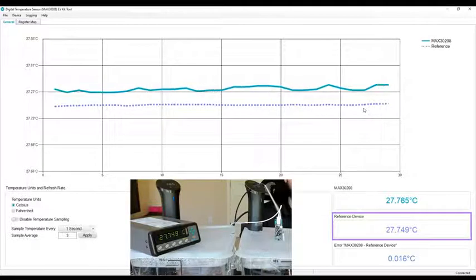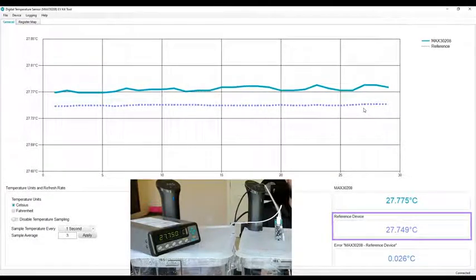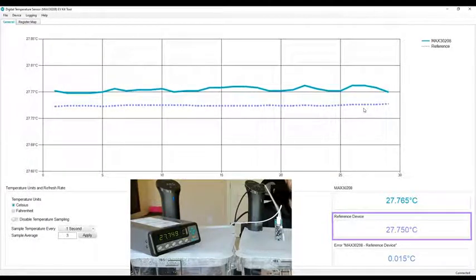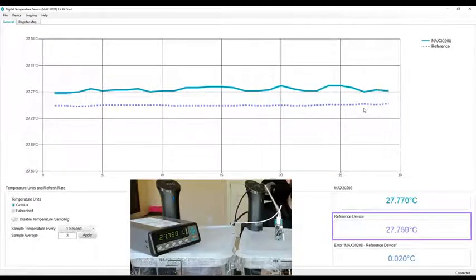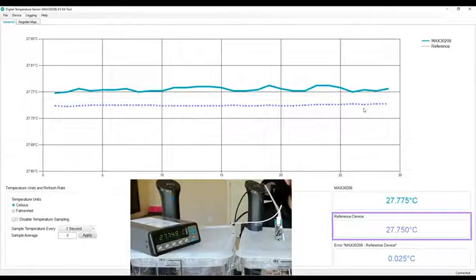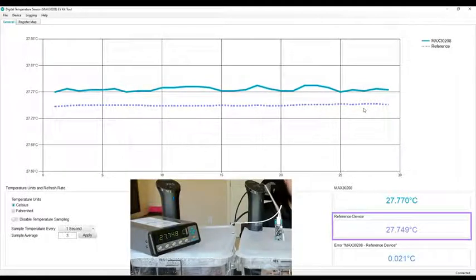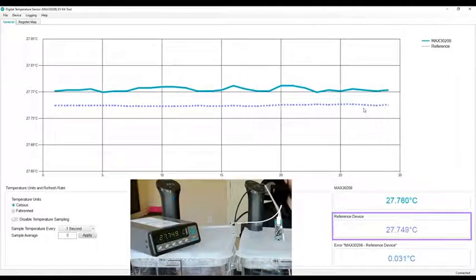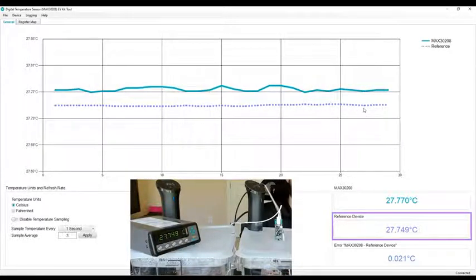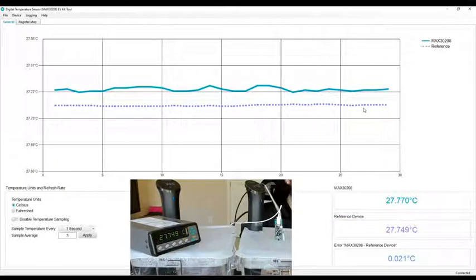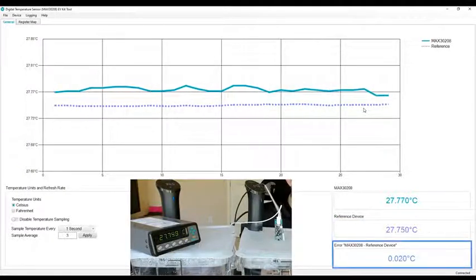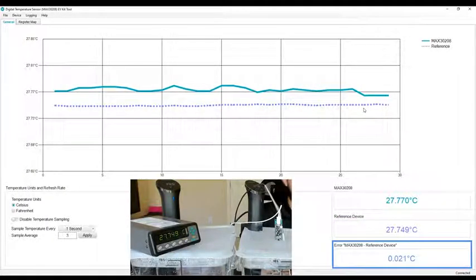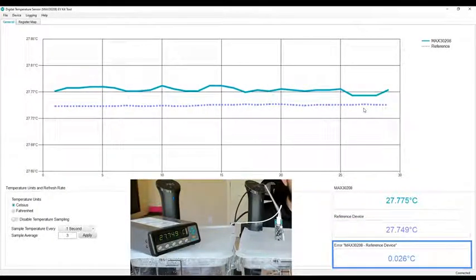This is a thousand to two thousand dollar piece of equipment. It's extremely accurate. So the number you're seeing there is what the temperature of the bath truly is. And then the third box on the bottom is the error—the difference between our device and the reference device.